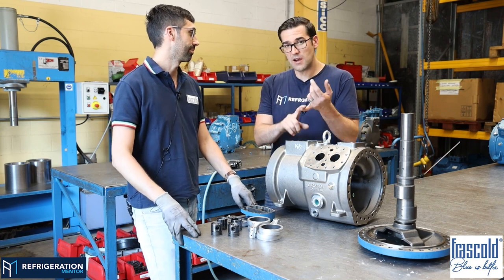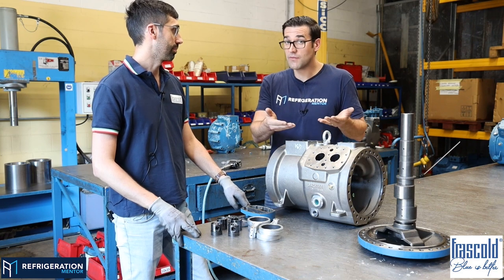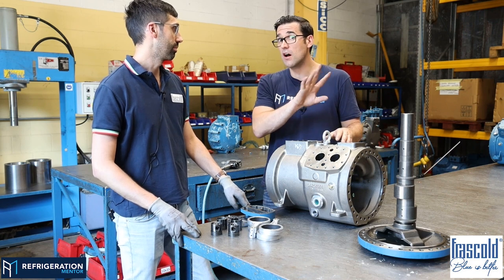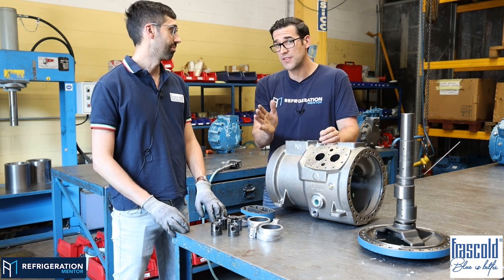So it could be a contactor, it could be a blown fuse for some reason. You have a bunch of refrigerant in there and it starts up on a locked rotor, and potentially blows one fuse and not all three, and that could lead to single phasing. And potentially there are lots of other things it could be.